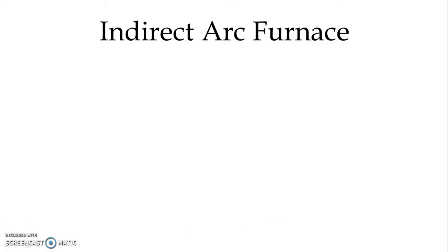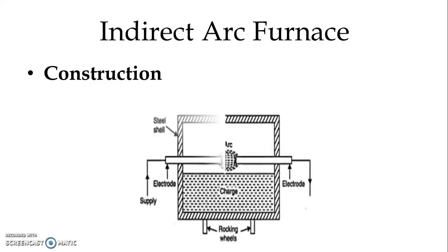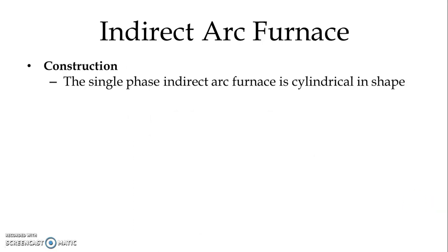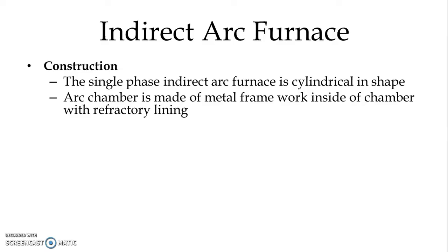Now let us study the Indirect Arc Furnace. The difference between direct and indirect arc furnace is that in case of indirect arc furnace, we use the arc generated between electrodes through radiation indirectly to heat the charge. Let us see the construction of indirect arc furnace. We have two electrodes for single phase. The arc is generated between the electrodes. The furnace has a cylindrical steel shell as the furnace body, and additionally we have rocking wheels. The arc chamber is made of a metal framework with refractory lining inside.